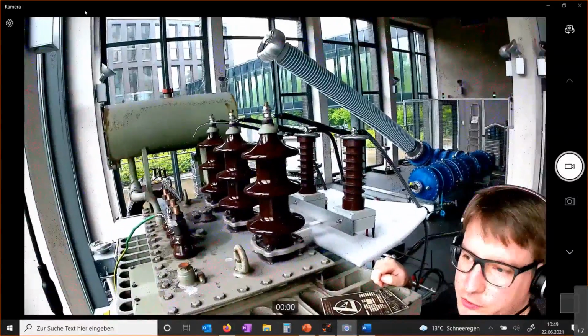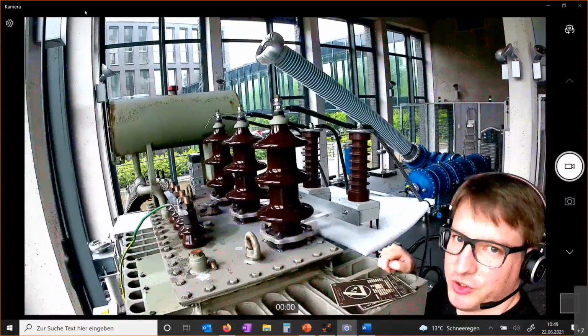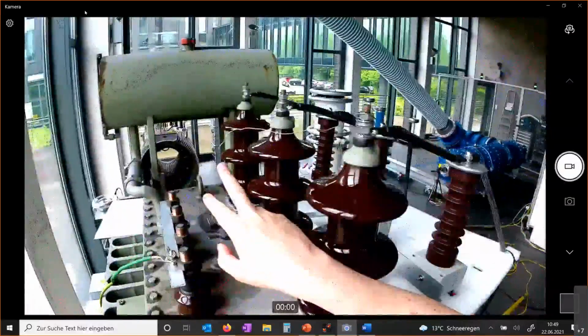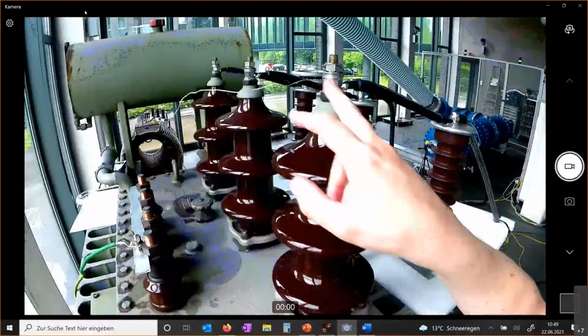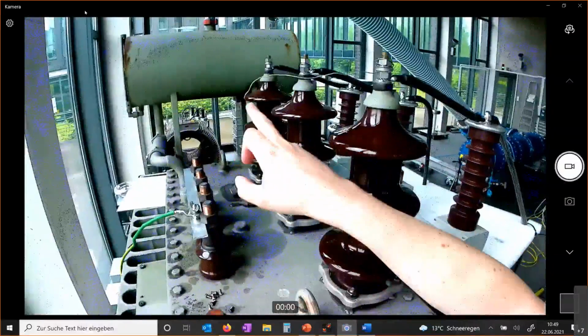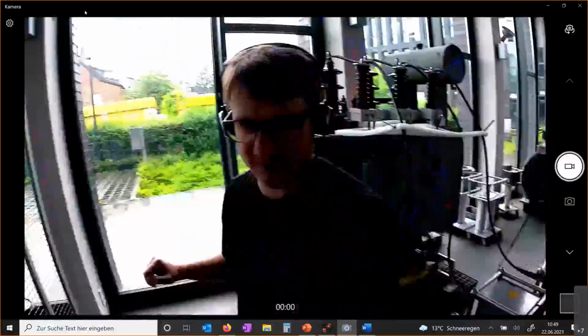One thing, sorry to interrupt you, Mohammed. One thing I forgot to show you, of course, is that the external corona activity that we saw was created by this wire, which is only connected to phase 1U. Yeah, sorry for interrupting you. No, great, thank you.